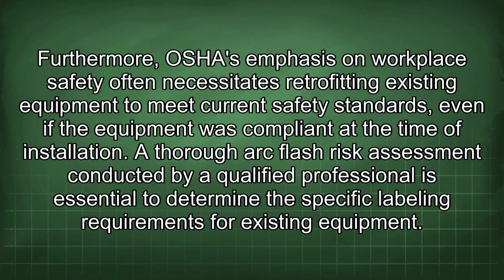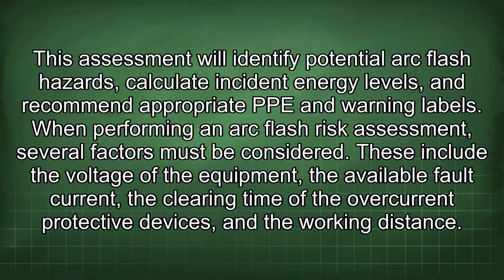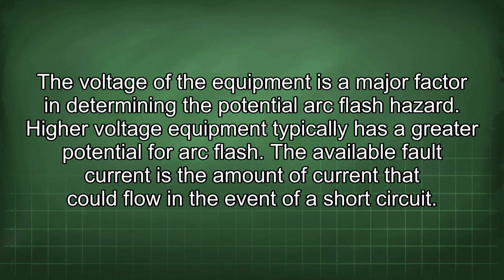A thorough arc flash risk assessment conducted by a qualified professional is essential to determine the specific labeling requirements for existing equipment. This assessment will identify potential arc flash hazards, calculate incident energy levels, and recommend appropriate PPE and warning labels. When performing an arc flash risk assessment, several factors must be considered. These include the voltage of the equipment, the available fault current, the clearing time of the overcurrent protective devices, and the working distance. The voltage of the equipment is a major factor in determining the potential arc flash hazard.